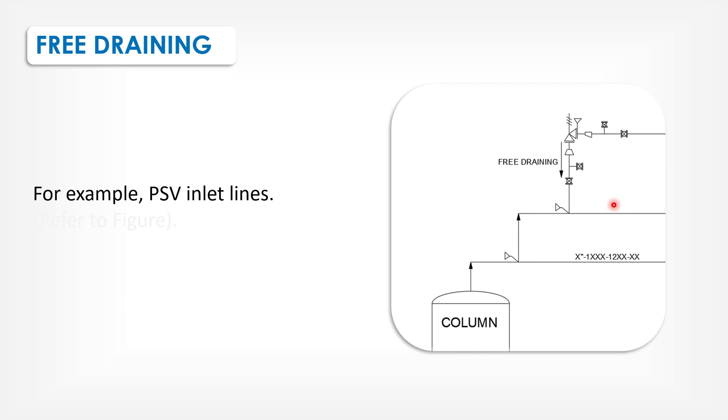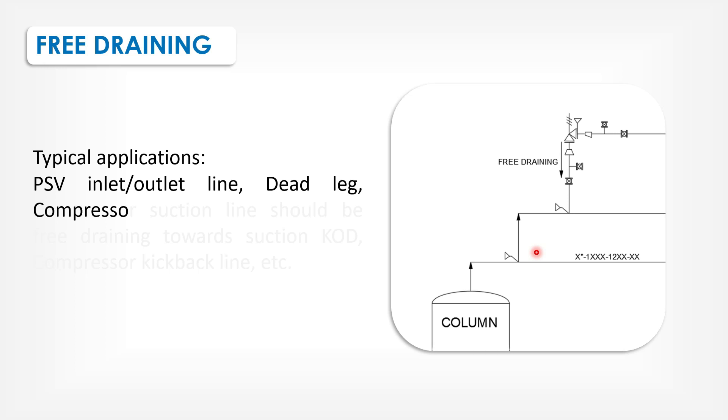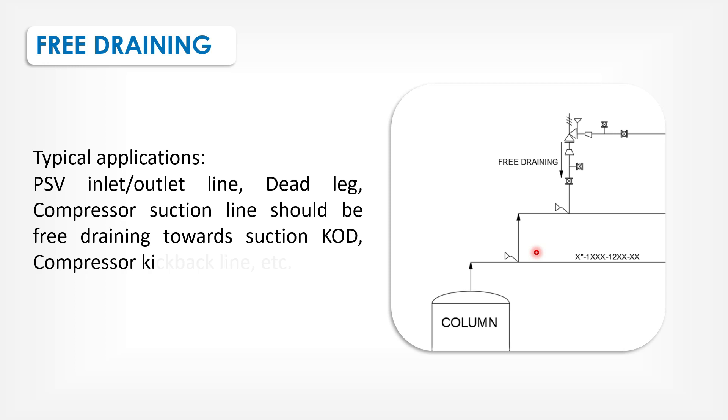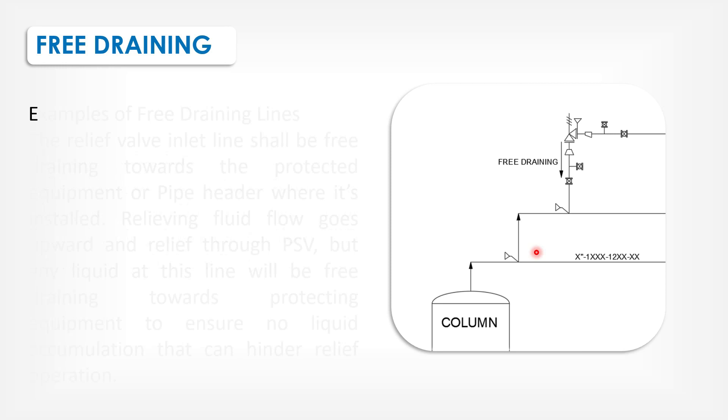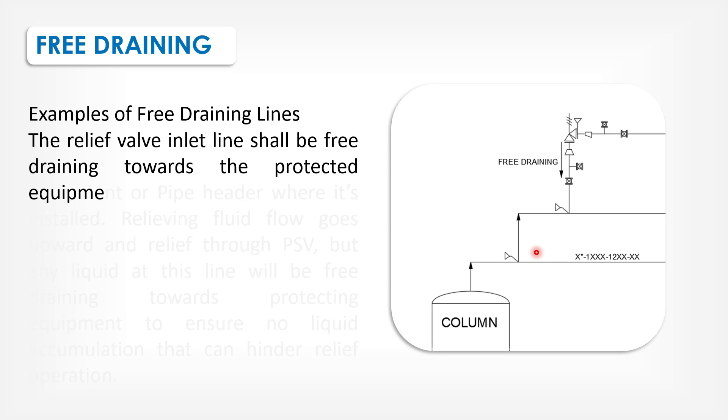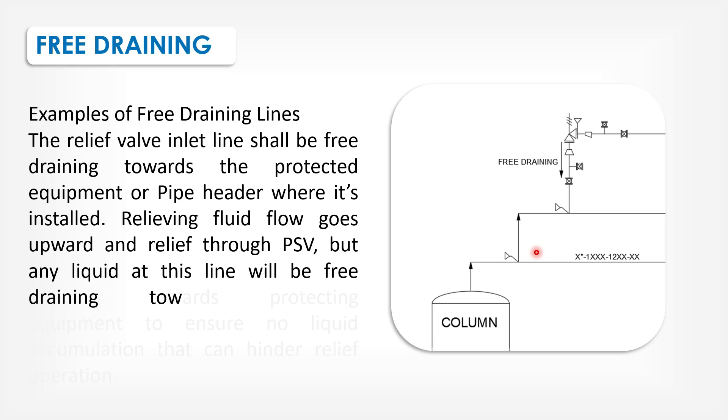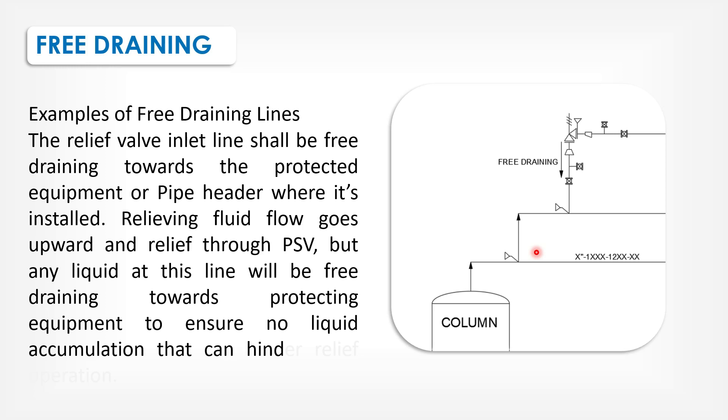For example, PSV inlet lines. The relief valve inlet lines should be free draining towards the protected equipment or pipe header where it is installed. Relieving fluid flow goes upward and relieves through PSV. But any liquid at this line will be free draining towards protecting equipment to ensure no liquid accumulation that can hinder relief operation.